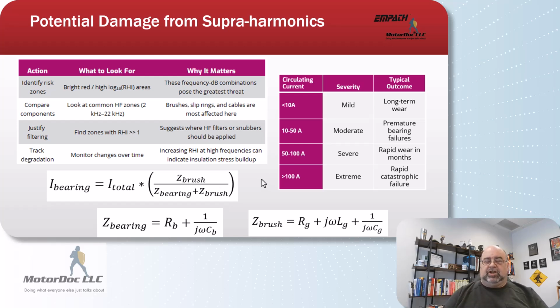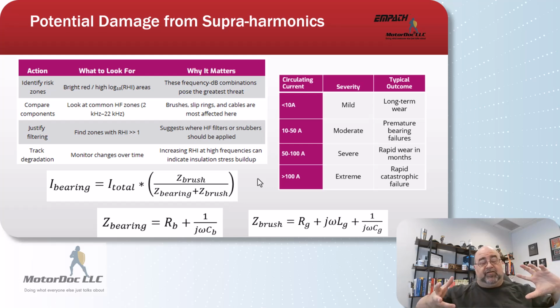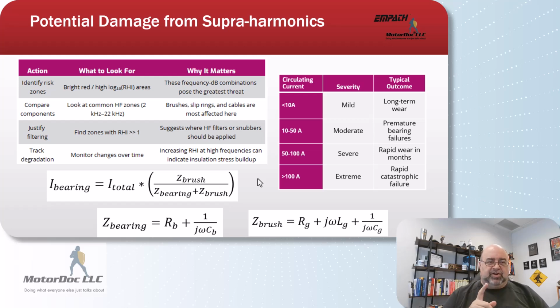Now, traditionally, and I don't know why, everybody says, oh, you have to take the voltage off the shaft, or you have to do all this stuff with the shaft. So you have to put yourself in extremely dangerous situations in order to gather data, when all you have to do is take a current clamp reading on ground. If you want, you can take a current clamp reading off the brush to see how much of the current is passing through the brush and how much is going to ground, and that'll give you the severity.